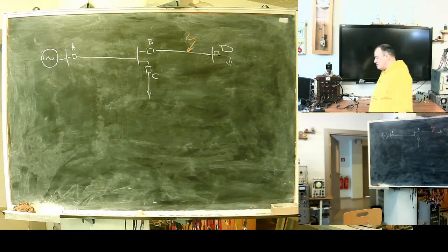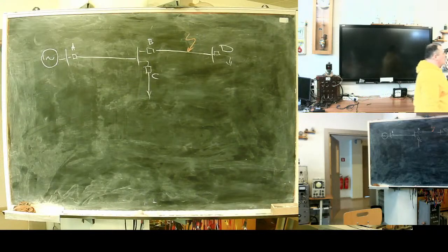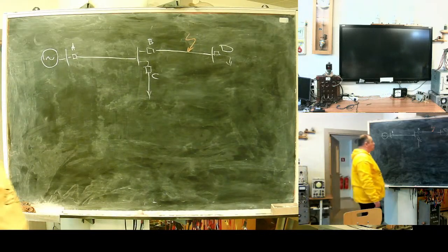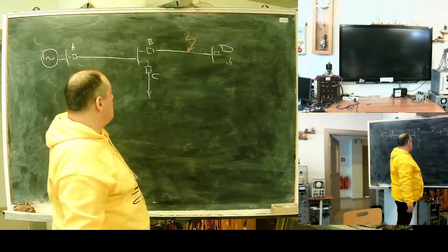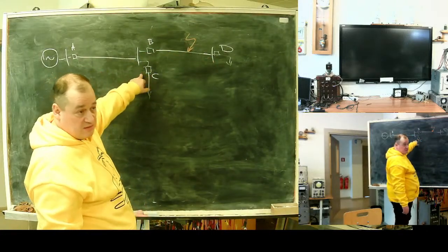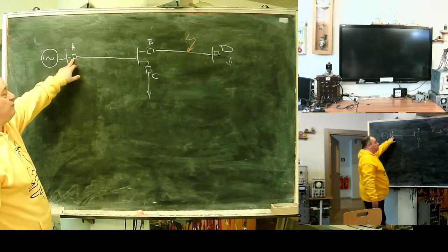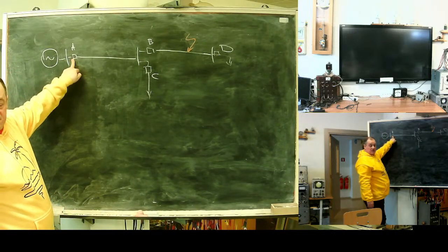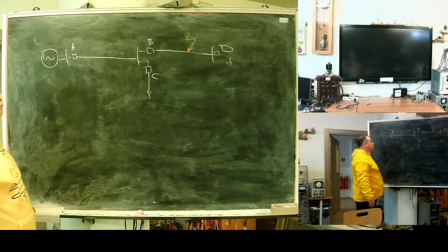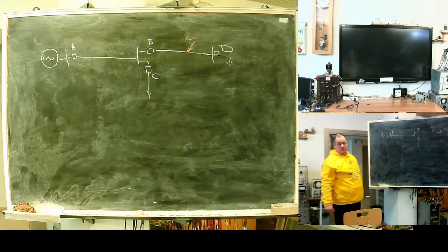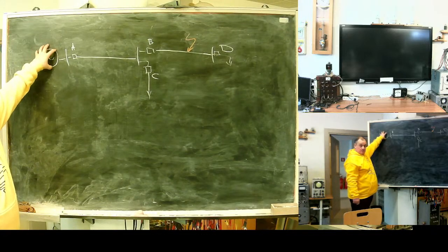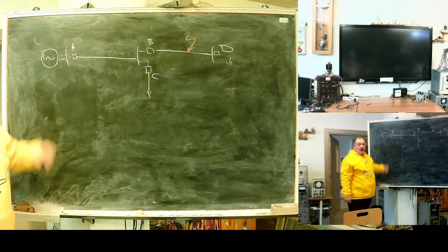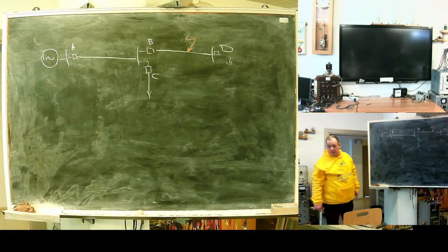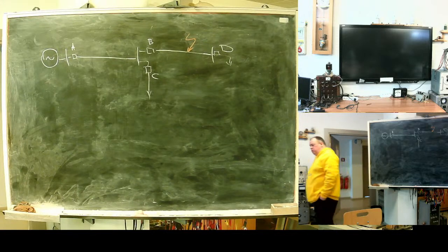I think B. Yes. It's closest to the fault in the current flow path. If I disconnect C, nothing happens. If I disconnect A, will the current disappear? No. Why? Do you see any more power sources here? The only power source. Yes. So if I disconnect A, I will clear the fault. But what's bad? Where's the problem? What will I lose?